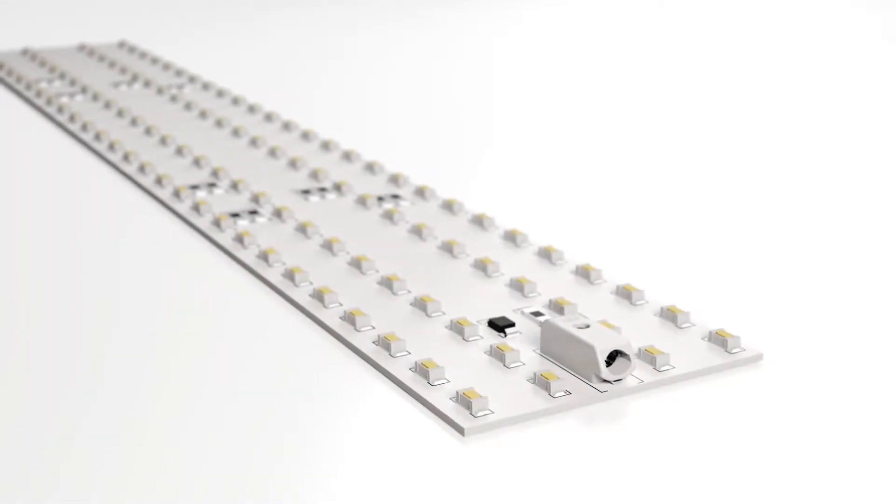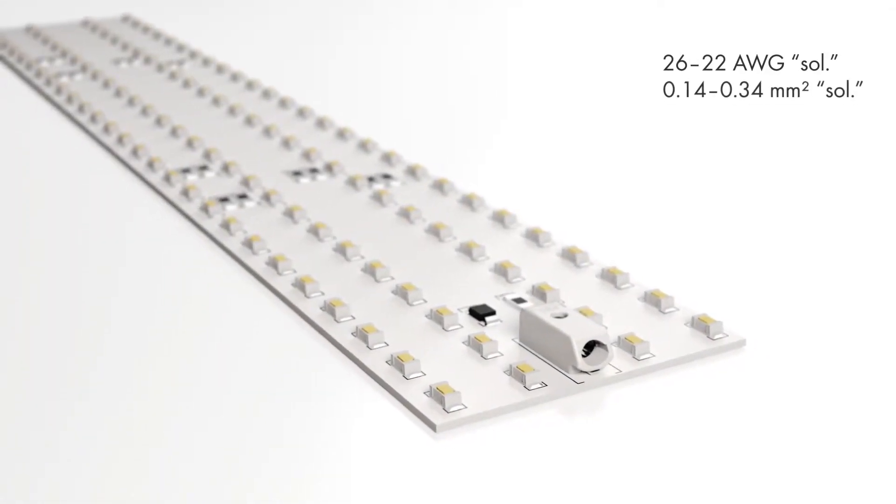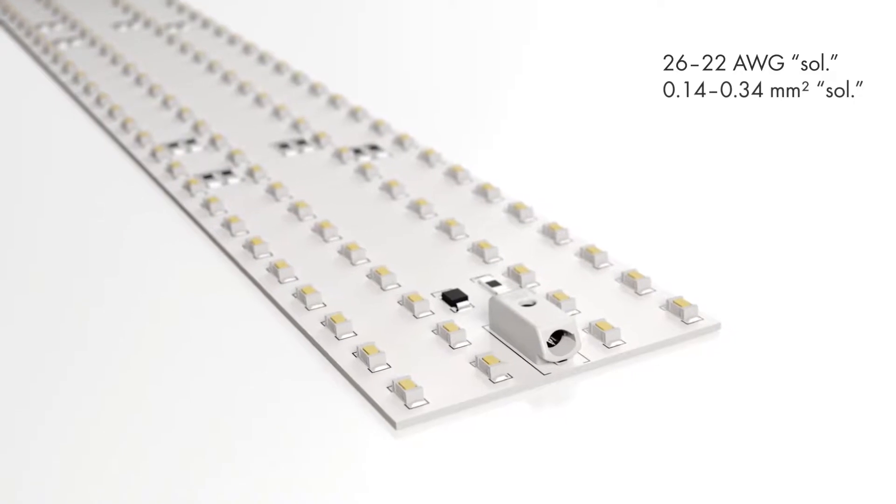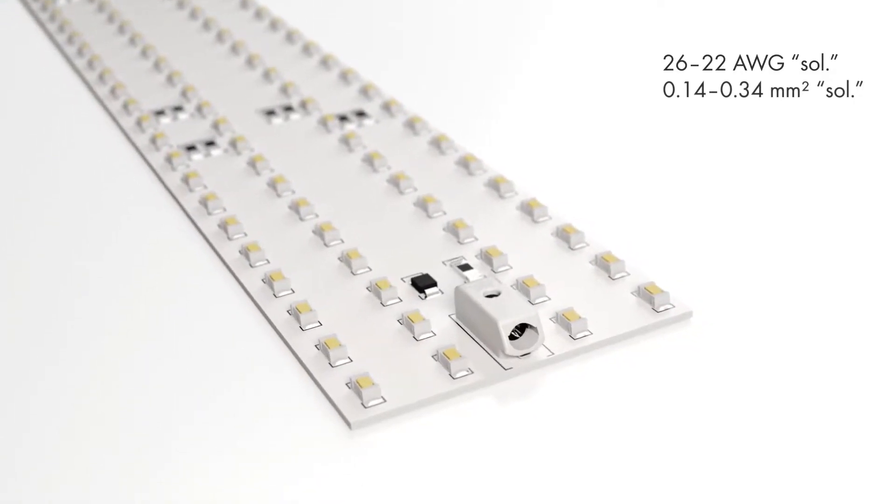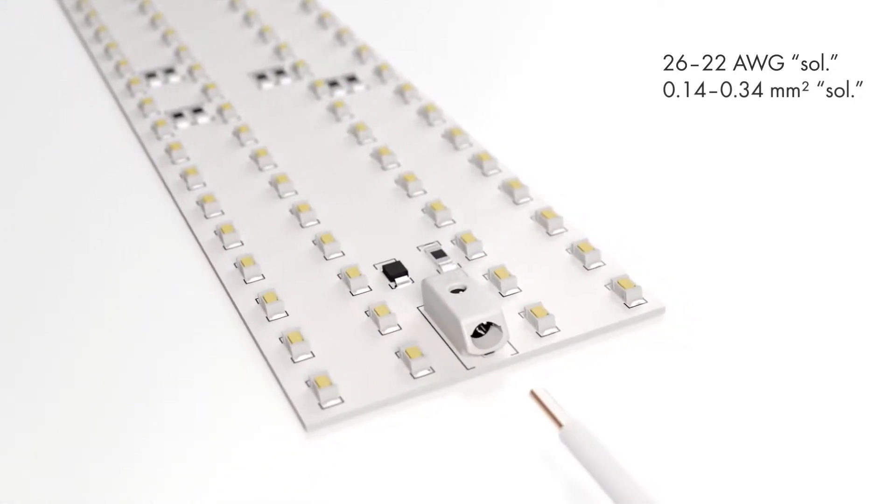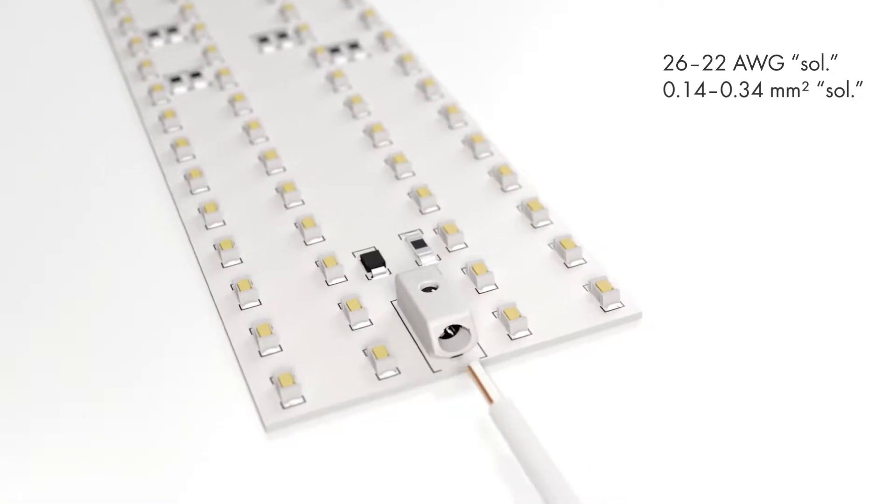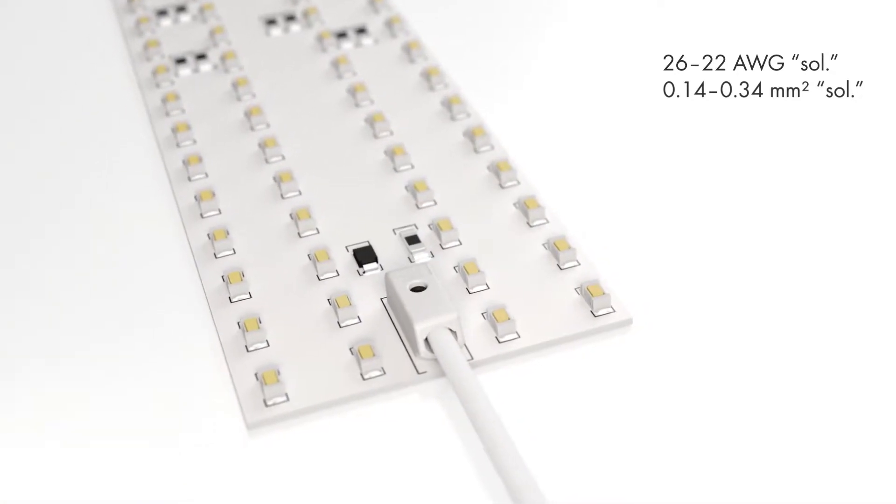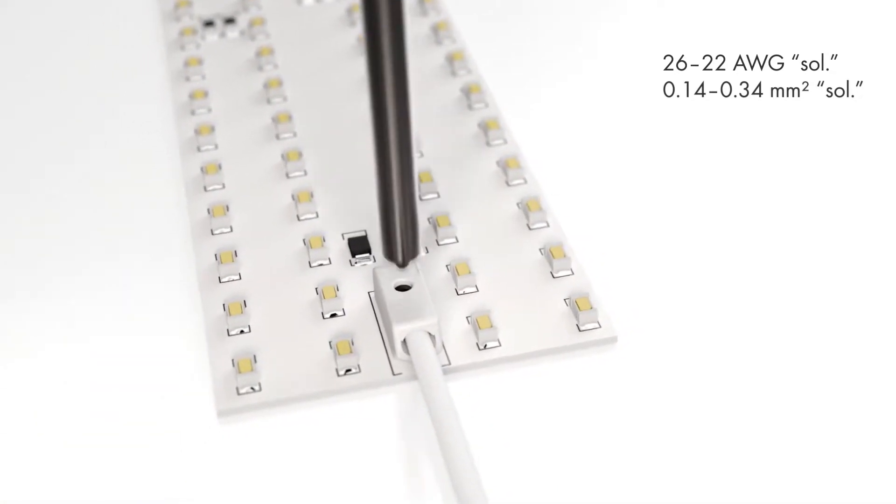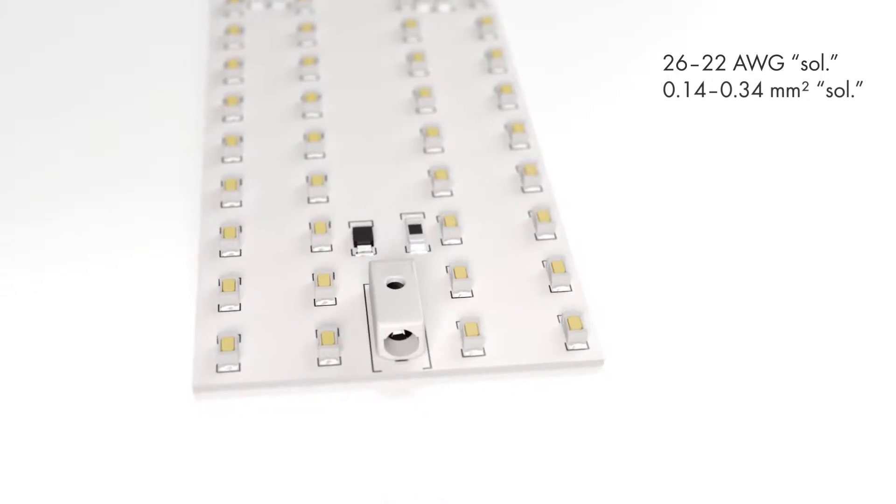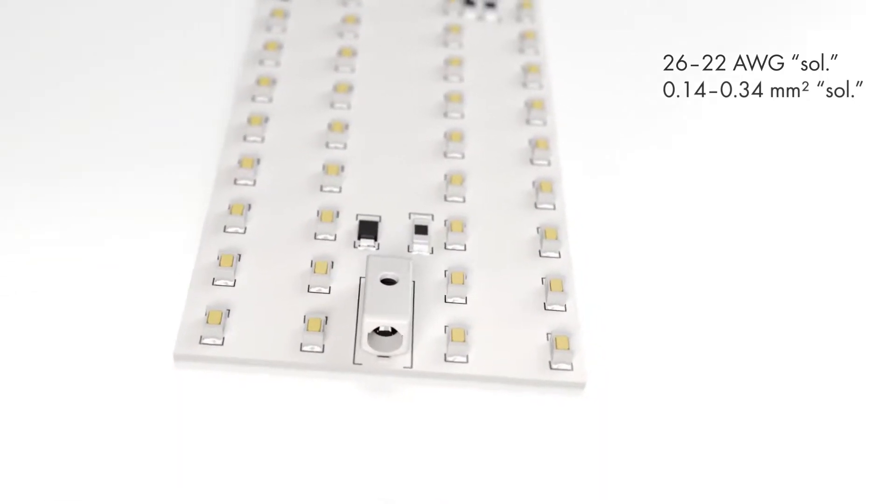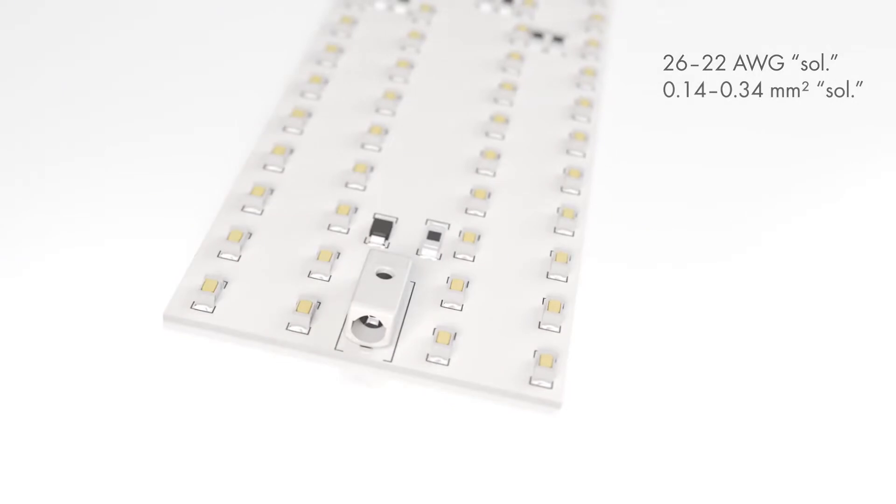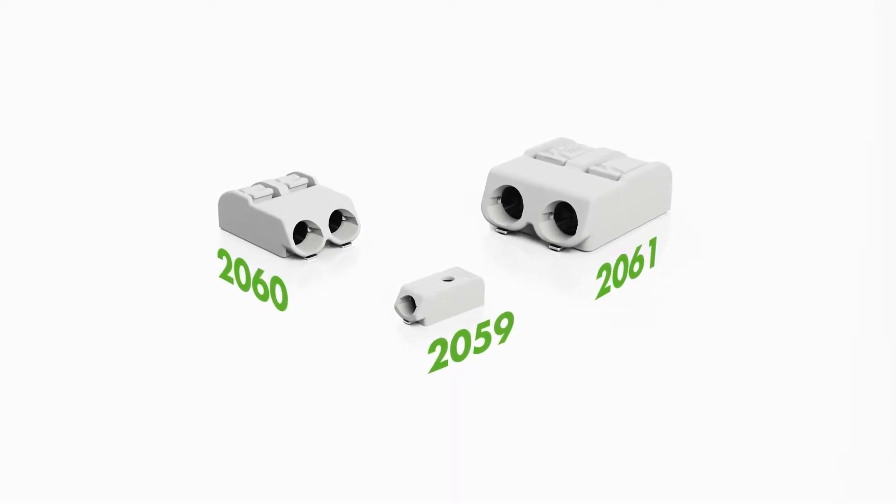The 2059 series PCB terminal blocks feature push wire connections making them very user-friendly. Solid conductors ranging in size from 26 to 22 AWG or 0.14 to 0.34 square millimeters are pushed in. Conductor removal is performed quickly using an operating tool to open the clamping unit.